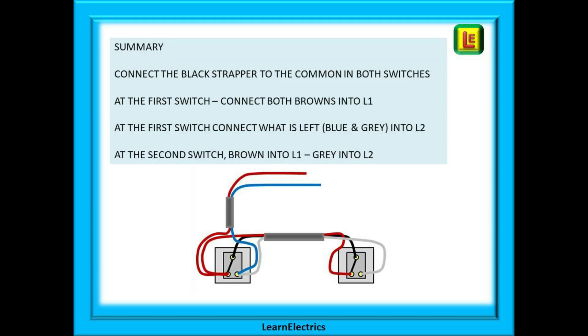We can have a quick summary of how to make the connections. They are very easy to remember. Connect the black strapper to the common in both switches. At the first switch, connect both browns into L1. And still at the first switch, connect what is left, blue and grey, into L2. At the second switch, brown into L1 and grey into L2. Job done. Finished.